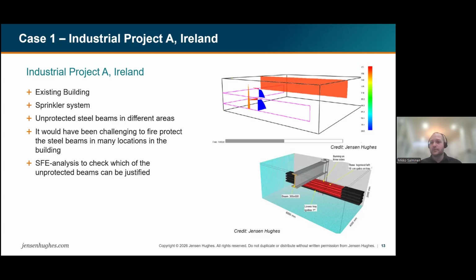So the process was first doing some fire simulations, like shown here in the figures. The actual fire load in many of the compartments was quite low, and the figure below shows a fire simulation model for a cable fire, where the cable racks, or cable trays, are below the steel beam. So that's the worst case scenario, and we had as much cable as possible in the model.